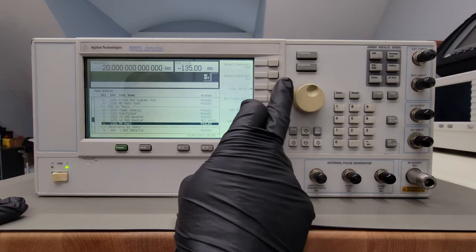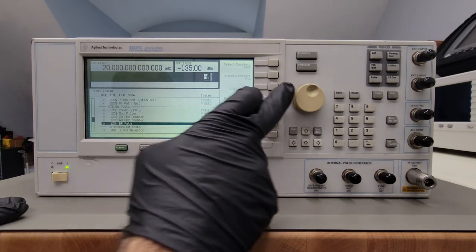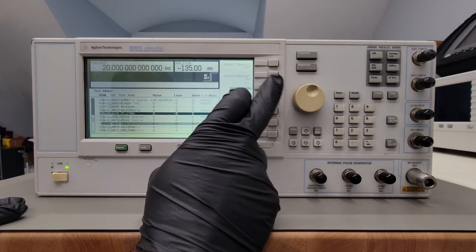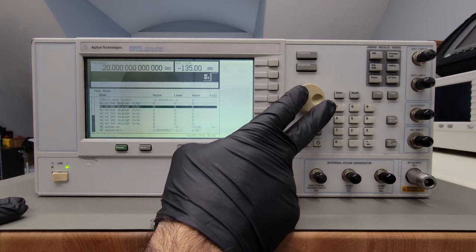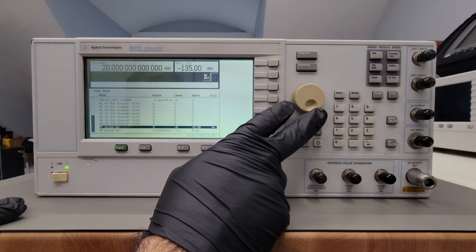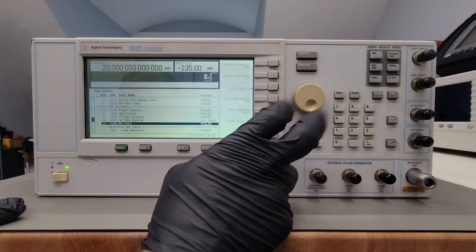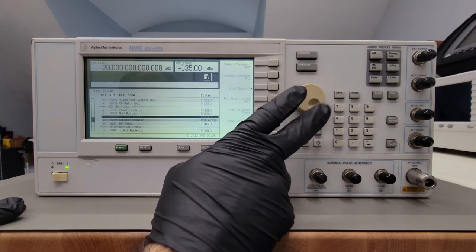Yeah, so the 1204 error is here, and that's related to the mid board specifically. But if we look at that error in detail, everything's good until we go to RF pulse on, and that's where the error is occurring. So everything else is fine.